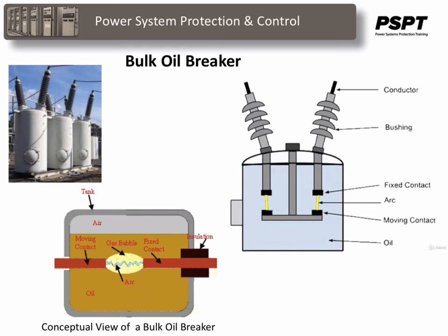The arc quenching in bulk oil circuit breakers takes place as the electric current passes through the zero crossing. As the gas bubble is enclosed by oil inside a totally airtight vessel, the oil surrounding it will apply high pressure on the bubble, which results in highly compressed gas around the arc. As the pressure is increased, the deionization of gas increases, which helps the arc in quenching. The cooling effect of hydrogen gas also helps the arc quenching in oil circuit breakers.